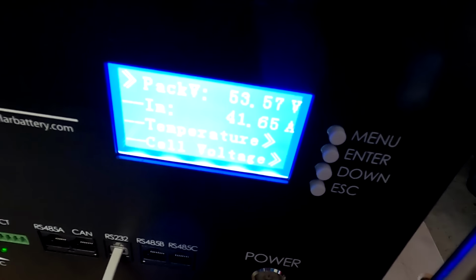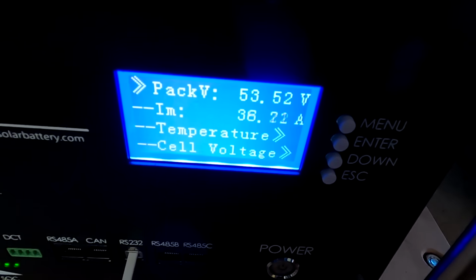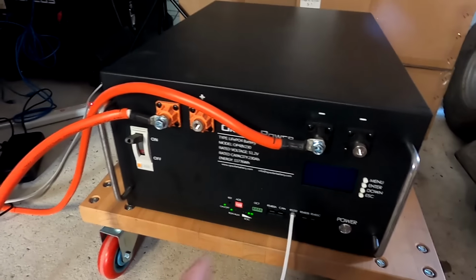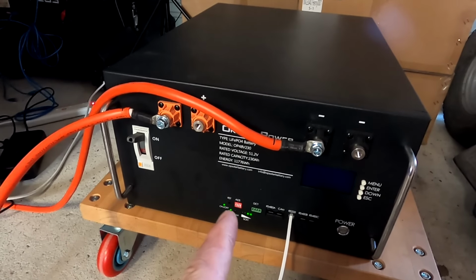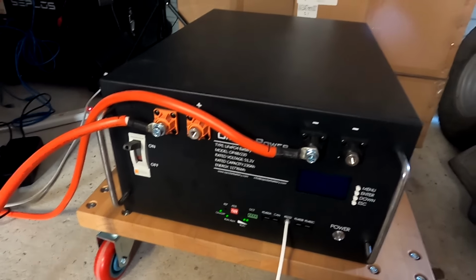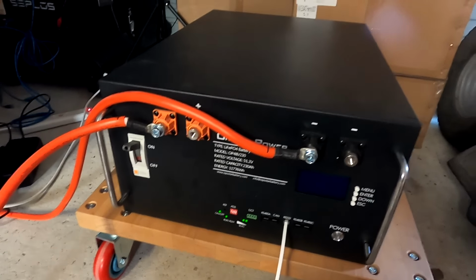All right, we see 50 amps, 44, 38. Yeah, that's the same here. So there's not too much happening. The voltage difference was not high enough to trigger anything. I think it needs the overcurrent protection actually to trigger the current limiter, because we reached the 50 amps and the current limiter didn't kick in. It probably takes until tomorrow night until this battery is fully charged. But that's fine, we wait until then, and then we do the full discharge test and see what we get.